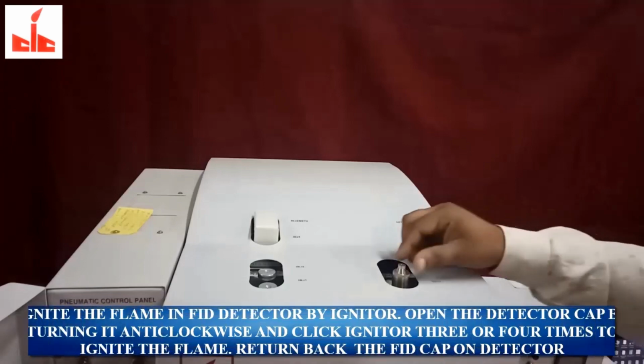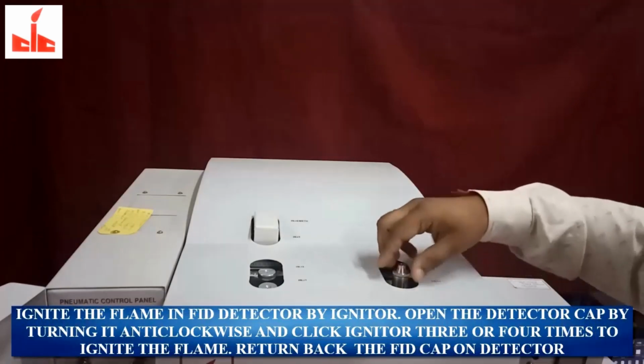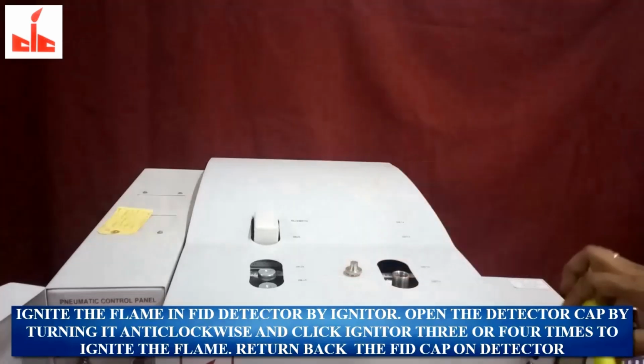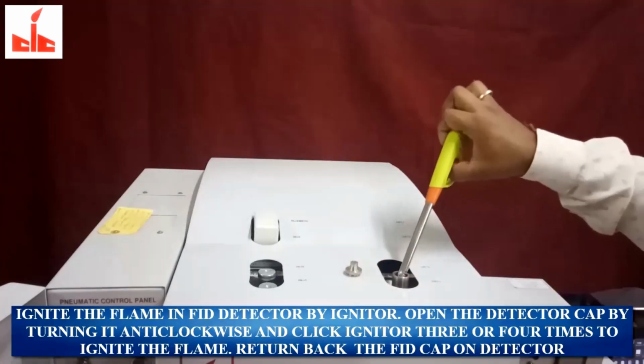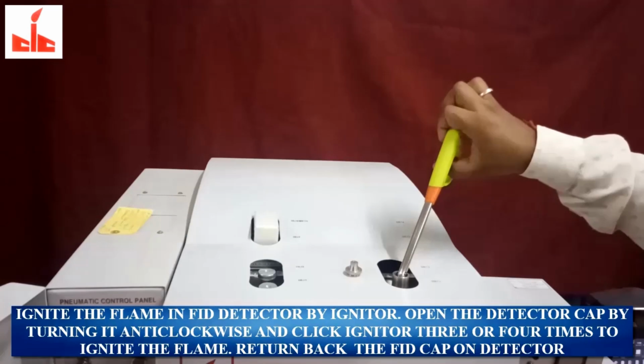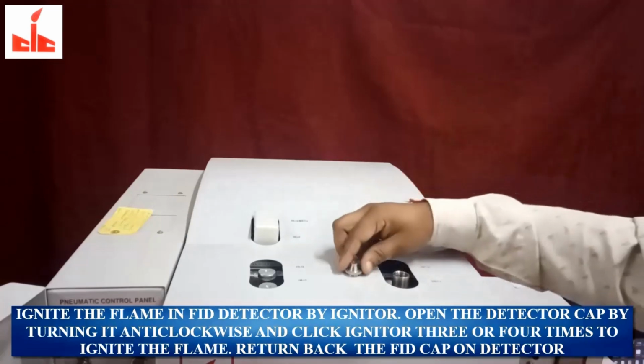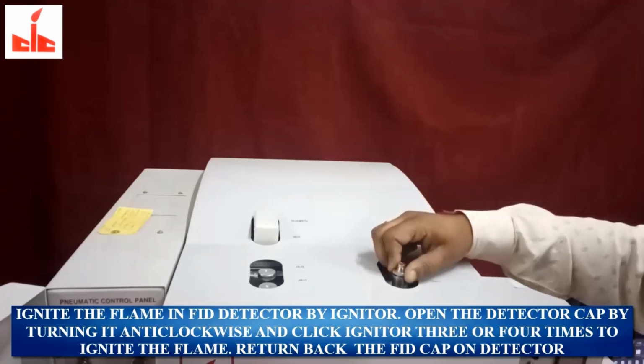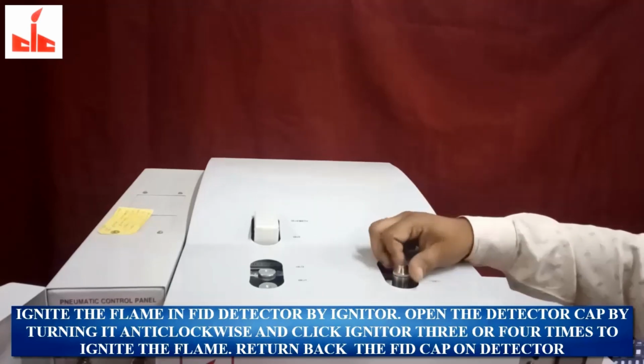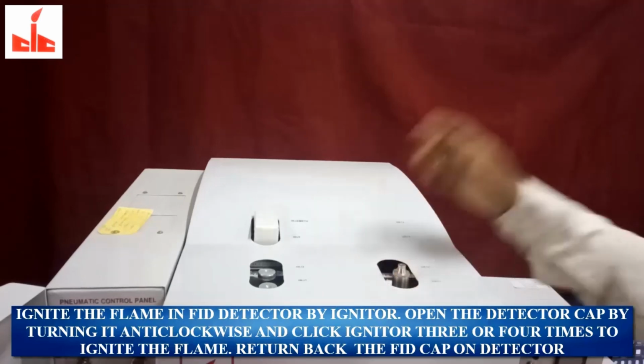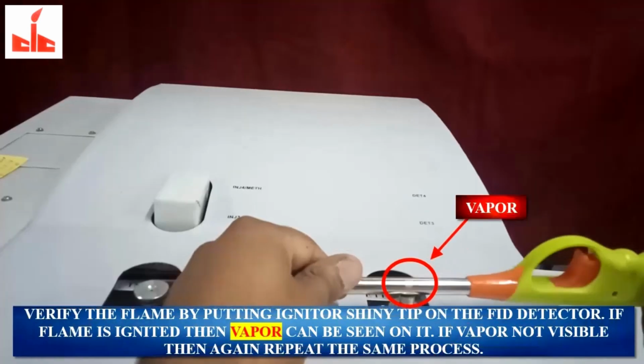Ignite the flame in FID detector by igniter. Open the detector cap by turning it anti-clockwise, and click igniter 3 or 4 times, to ignite the flame. Return back the FID cap on detector, by turning it clockwise. Do not over-tight the cap, just stop turning when threads are finished.